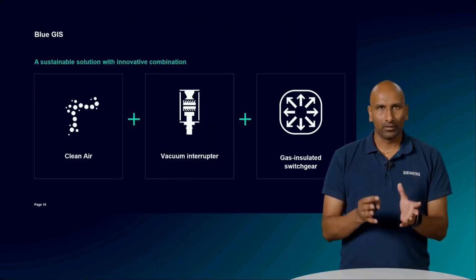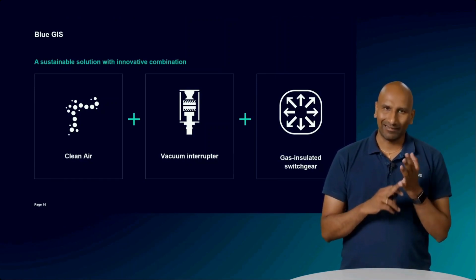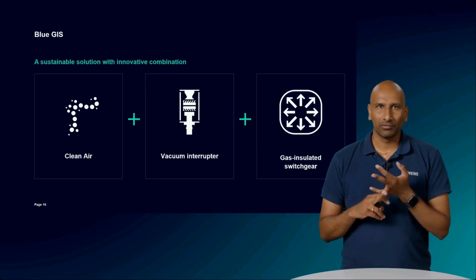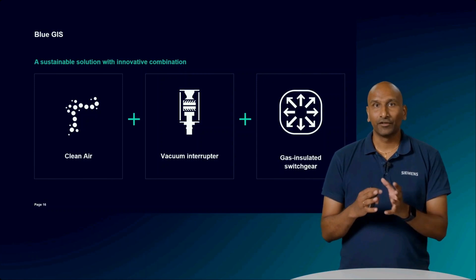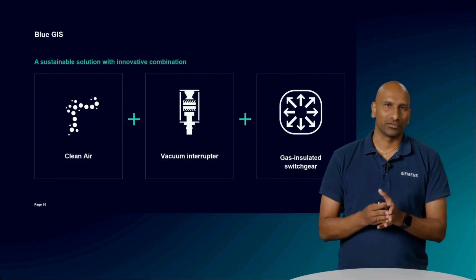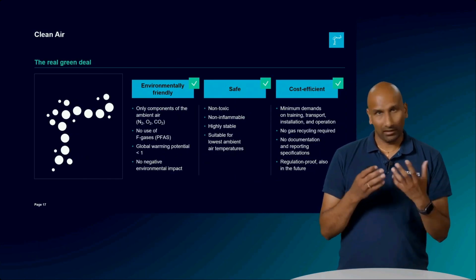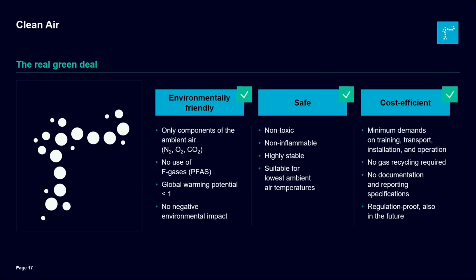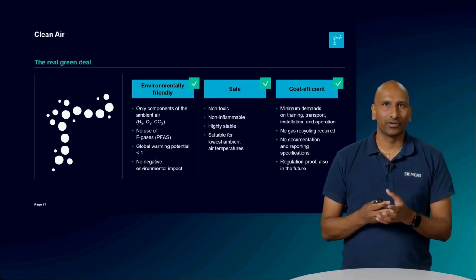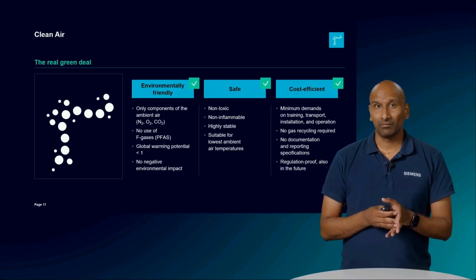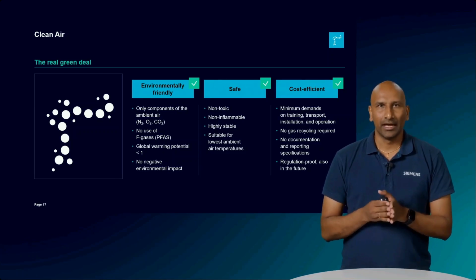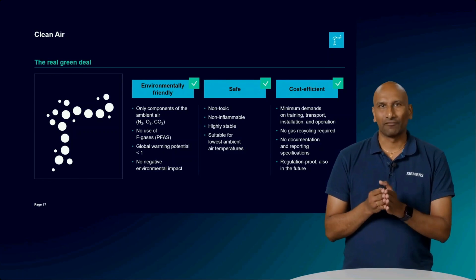As an overview, our Blue GIS is the combination of clean air as an insulating medium, vacuum interrupters for interruption of currents, and all the features of a traditional gas-insulated switchgear. The clean air we use is made up of natural origin gases with global warming potential less than 1. It contains no F-gases, making it very safe to operate, which enables easy handling during the lifetime of the switchgear. This insulating medium also has no regulatory restrictions, and no documentation or reporting is required for this gas.